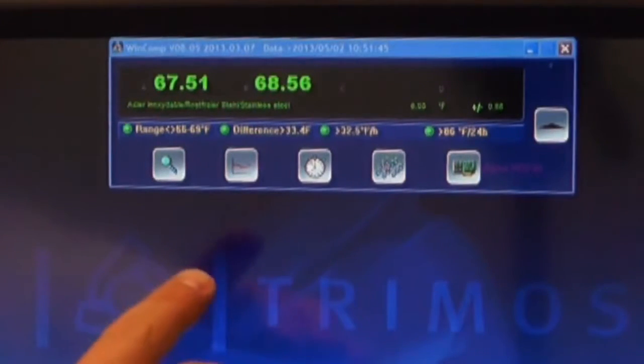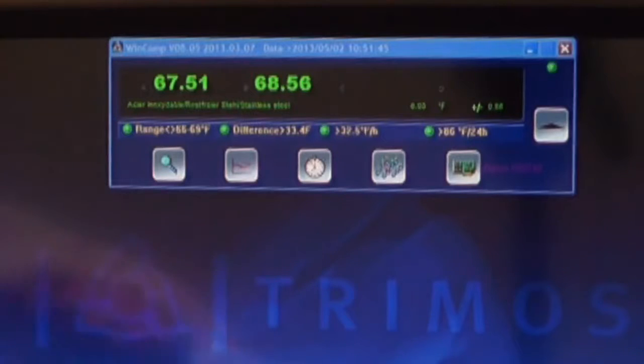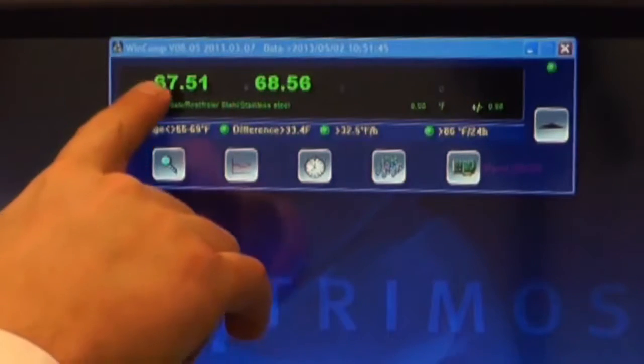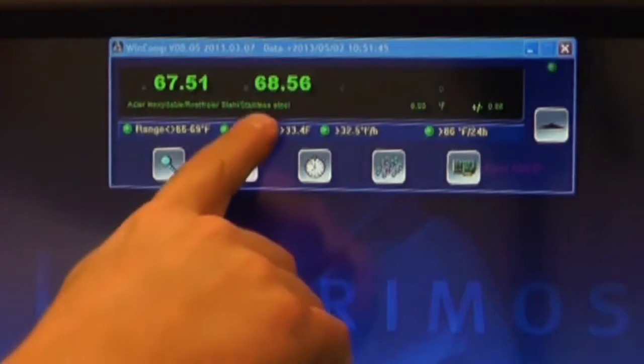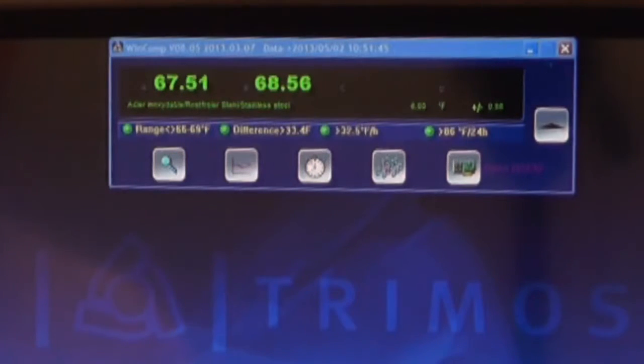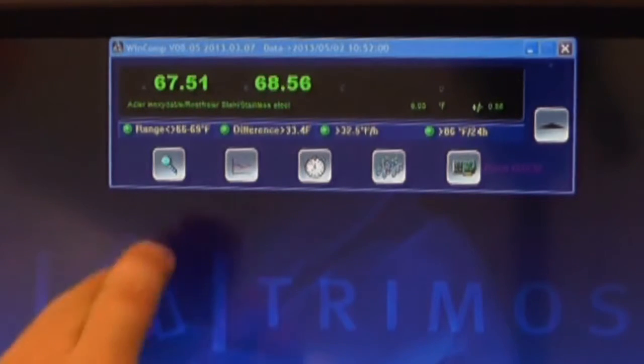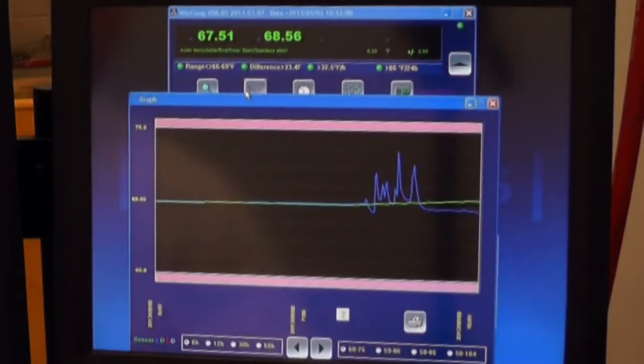On the right screen at the top is WinComp. This is our temperature compensation unit. Here you can see the readout for the temperature of the scale and the current temperature of the movable temperature probe, which will be attached to any piece being measured. This can also be used to graph temperature data over time, and can be set up to send alerts if the laboratory temperature goes outside of certain bounds.